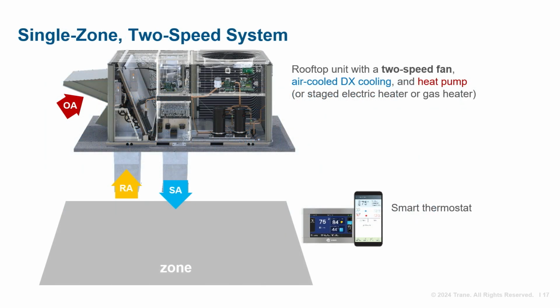The supply fan operates at a high or low speed setting. A thermostat in the zone is used to determine how much cooling or heating is needed. The rooftop unit is cycled on and off to provide cooling or heating, while the fan is adjusted between high and low speeds to maintain the zone temperature set point. Finally, the outdoor air damper position is set to introduce the required CFM of outdoor air for ventilation, adjusting its position as the fan speed changes between high and low. Or this damper might be opened further when it's cool outside for airside economizing.